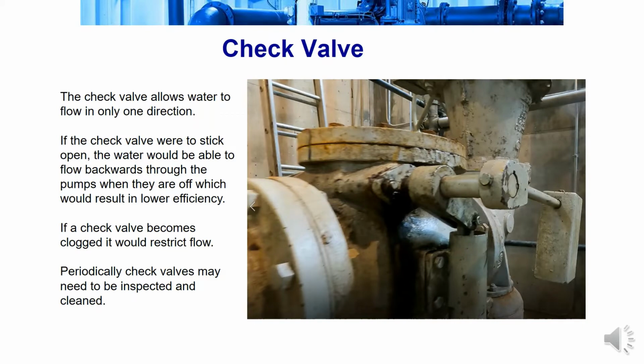The check valve allows water to only flow in one direction. The picture here is an example of one of the check valves within this location. If the check valve were to stick open, water would be able to flow backwards through the pumps, which will result in lower efficiency. Or if the check valve becomes clogged, it will also restrict flow out of the pump. These check valves need to be periodically inspected and cleaned, and should be part of a maintenance schedule.